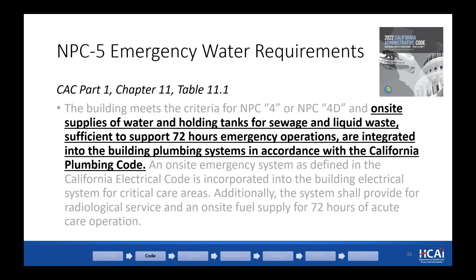California Administrative Code has a definition of NPC 5 under Chapter 11, Table 11.1. It essentially states a building that has its non-structural components braced, that is NPC 4 or 4D, and has on-site supplies of water and holding tanks for sewage and liquid waste, sufficient to support 72 hours of emergency operations, and are integrated into the building plumbing systems in accordance with the California Plumbing Code. There is also discussion on the e-power requirement as it's shown in the text, which is not highlighted in the slide. Again, the intent of an NPC 5 facility or building is to have the facility self-sufficient without any external resources for the initial 72 hours after a disaster or an earthquake.